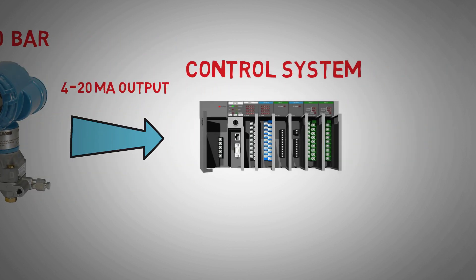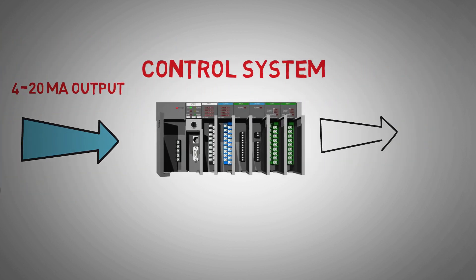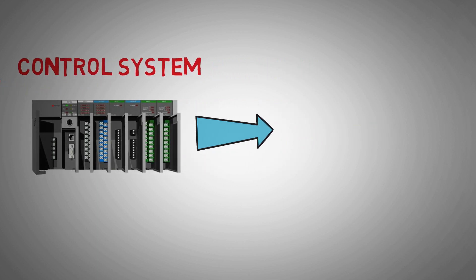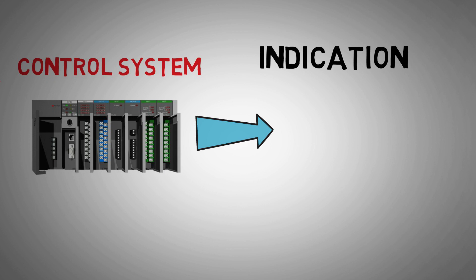This 4 to 20 mA signal is then interpreted by the control system and can action different events, such as indication of process variable, an alarm or action when the process variable is over or under a certain set point, or altering a valve position on plant to control the process variable.